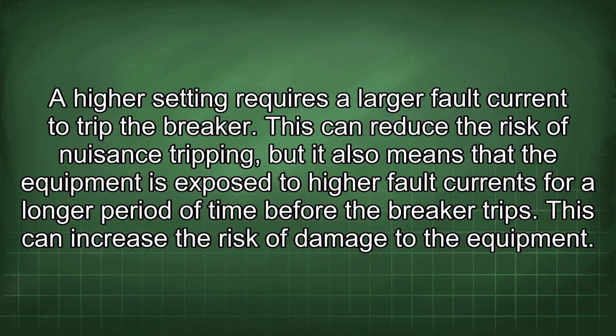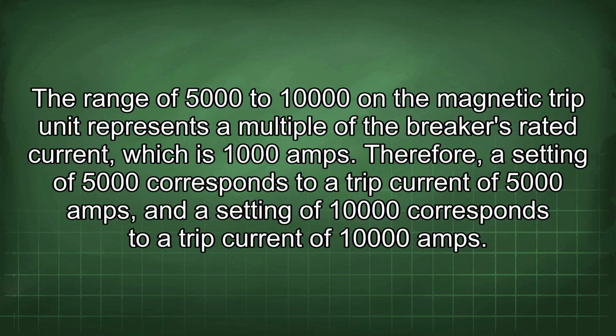A higher setting requires a larger fault current to trip the breaker. This can reduce the risk of nuisance tripping, but it also means that the equipment is exposed to higher fault currents for a longer period of time before the breaker trips. This can increase the risk of damage to the equipment. The range of 5,000 to 10,000 on the magnetic trip unit represents a multiple of the breaker's rated current, which is 1000 amps. Therefore, a setting of 5,000 corresponds to a trip current of 5,000 amps, and a setting of 10,000 corresponds to a trip current of 10,000 amps.